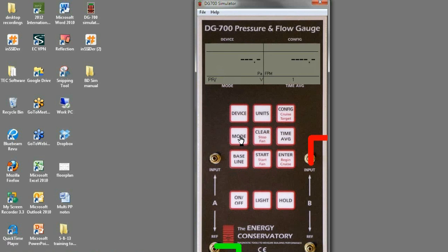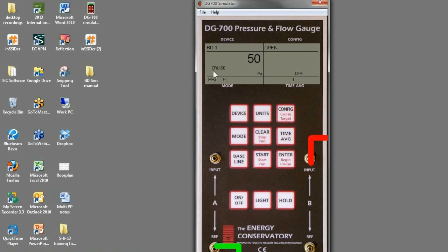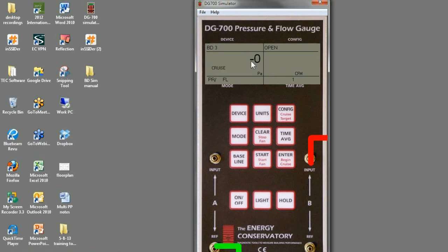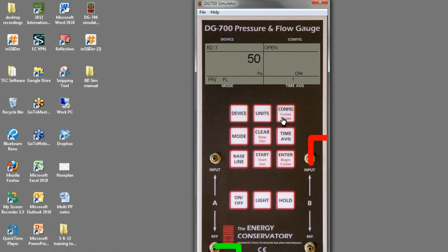But if we change our mode to pressure flow, it'll let us adjust that target. So if I hit begin cruise, we've got cruise flashing. We've got 50 as our default. We can change our cruise target to 25, 0, or negative 0. 0 and negative 0 come into play depending on if we're cruising a positive or a negative pressure. We have to know on which side is 0 to speed up the fan and which side of 0 to decrease the flow of the fan. So there is a difference if we want to cruise 0 or negative 0. And then once we've chosen our cruise target, we simply hit start fan.